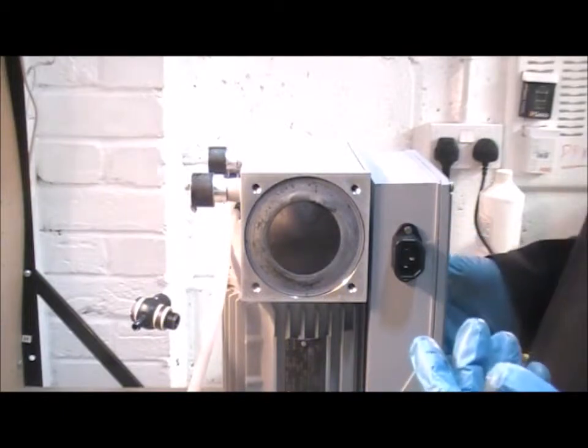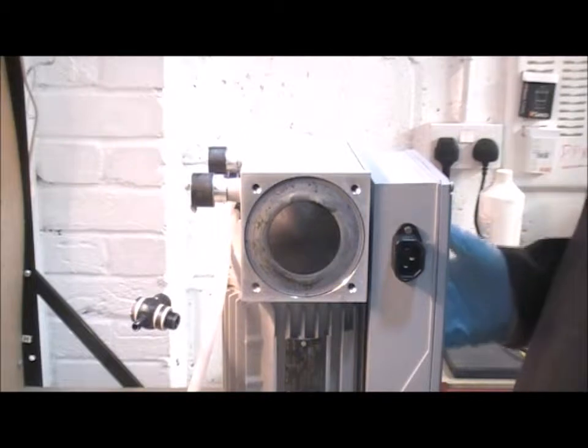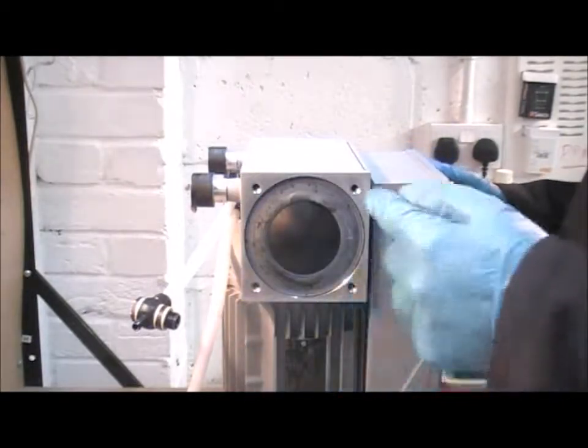On this pump I've mounted it so that the shaft is vertical. On this particular type of pump it's a little bit easier to do if you get them that way round. You can see I've undone the four bolts, removed the head, and here's the damaged diaphragm.